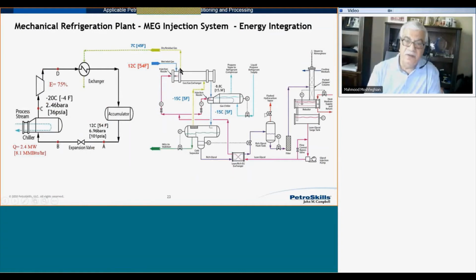So let's use this criteria. Remember, I had a residue gas from the dew point control, and this residue gas goes to a compressor. Again, typically it goes to compressor, and compress, and then from there goes to gas pipeline. But this is from offshore platform production. The environment temperature is cold enough, so we can use this as a cooling media for the condenser of my simple refrigeration plant. So instead of air or water, I'm going to use this cold process gas, which is available as my cooling medium for condenser of my simple refrigeration plant. So let's see how much the power requirement for compressor goes down.